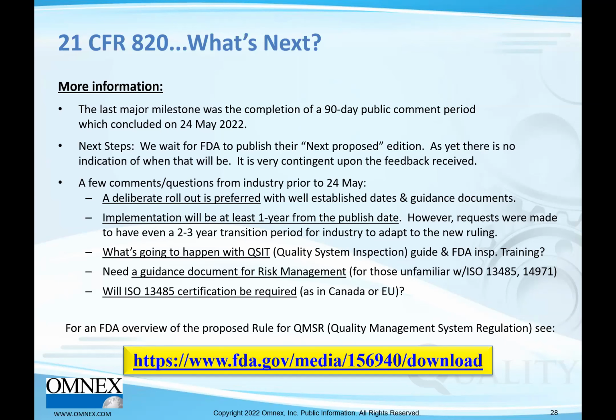Last question, and I think this might be one of the most important. Will ISO 13485 certification be required as it is in the UK, Canada, or the European Union? Right now, the answer is no, it's not in the proposals. That could change. You don't need to be certified to a system to comply. For example, the FDA does not require your company to be, quote, approved by the FDA. The FDA does not approve a company. You just need to comply with its rules. And I think that's all the FDA is requiring here, that you conform or comply.